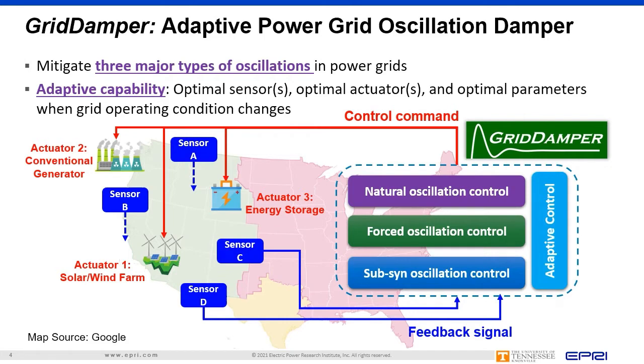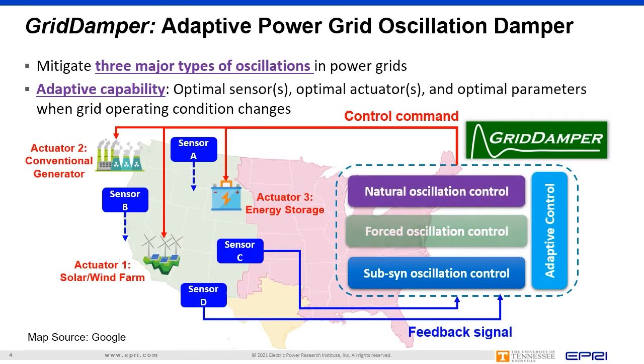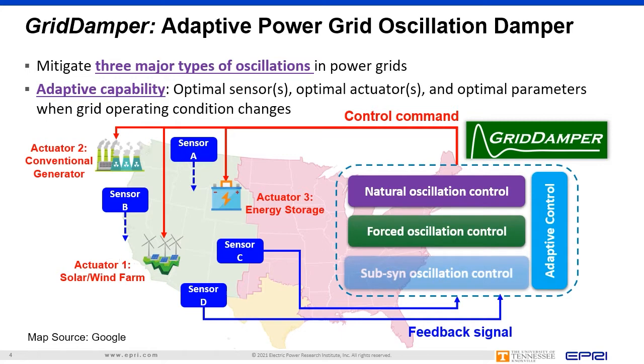Grid Damper is a disruptive technology. Its innovative design enables the mitigation of three major types of oscillations: natural oscillations by intrinsic system characteristics, forced oscillations driven by external periodical sources, and sub-synchronous oscillations caused by interactions between renewable plants and the power systems. The adaptive capability of Grid Damper guarantees optimal control performance under varying power grid operating conditions, adaptively choosing optimal sensors and actuators and automatically updating the control parameters.